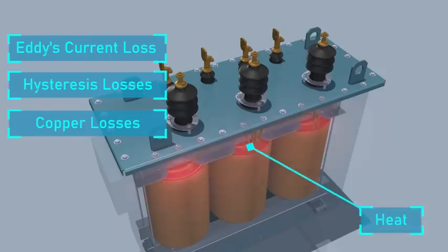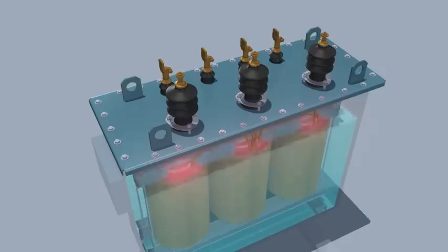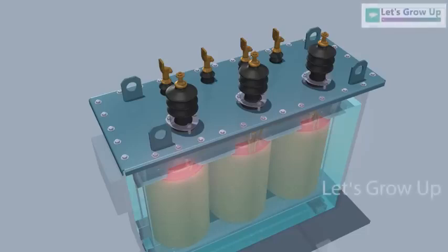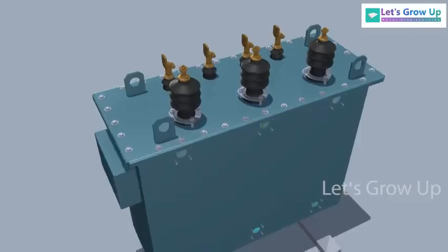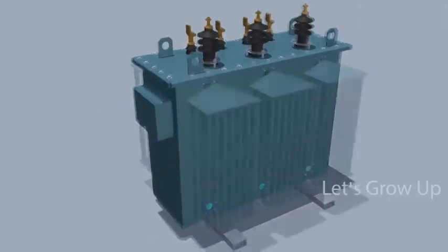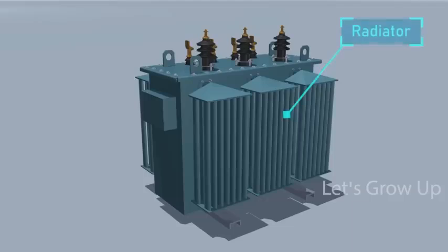To prevent heat, transformer oil is used inside the tank. The main role of transformer oil is to act as a coolant and to insulate. Transformer oil is an exceptional heat conductor, and can effectively reduce the copper coil's temperature, stopping them from burning. Not only that, external cooling tubes or radiators are there. The radiator of the transformer accelerates the cooling rate, thus it plays a key role to increase the loading capacity of an electrical transformer.